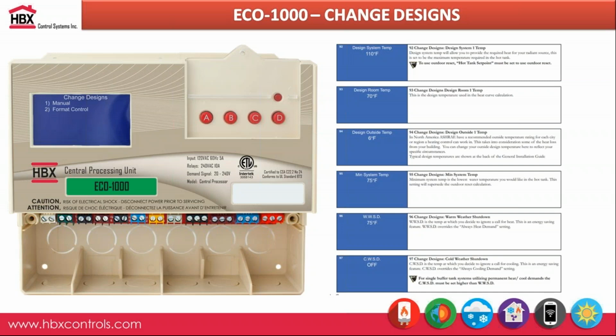You also have the ability to put in a minimum system temperature, so your system will never go below that. And then you have the options to put warm weather and cold weather shutdown on there. If you're just utilizing this controller to control one single tank system, once the controller goes into a warm weather shutdown, it automatically changes that buffer tank over to cooling, and vice versa. If it gets out of cold weather shutdown, it goes into the heating option.